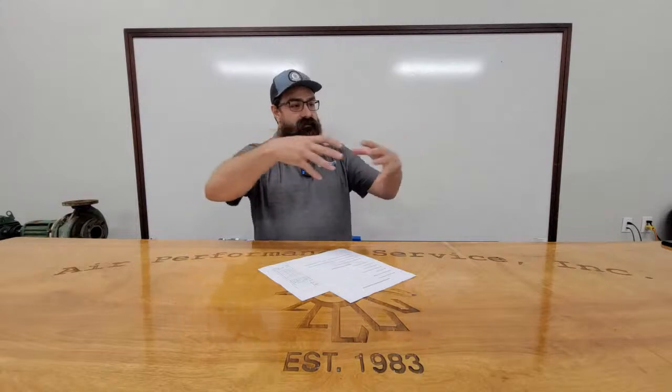You want to let it run and level out and see what you're going to get before you bring on the next one. And then if you're doing return temp control versus discharge, that's a much broader loop. It's going to be a lot slower acting because you're affecting the whole space instead of just the air coming out of the coil, right? A discharge loop is going to be much faster reacting than a return loop because you have a lot bigger process environment to control. You're talking about circulating air and pulling it back through, whereas just controlling right off the coil, a lot less variables. So actually a lot more variables in a return, because you've got all the space to circle through and heat loads and things like that. Whereas off the coil, you're just controlling on that one variable.